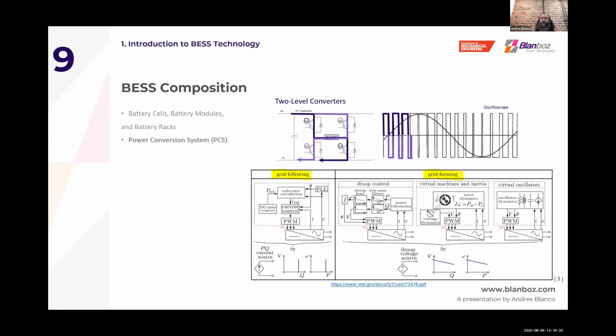I still don't know what the actual issue was, but my first gut feeling was that there was a lack of inertia, because that's very common. Controlling inertia is very difficult, and inertia mainly comes from synchronous machines. So the beauty of grid-forming now is that we can supply inertia from this grid-forming equipment. You may hear terms like virtual or synthetic inertia, or virtual synchronous machine—I know many electrical engineers don't like that term, but anyway, the key point is you have grid-following and grid-forming.